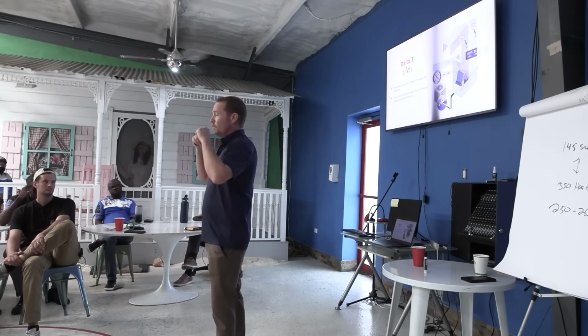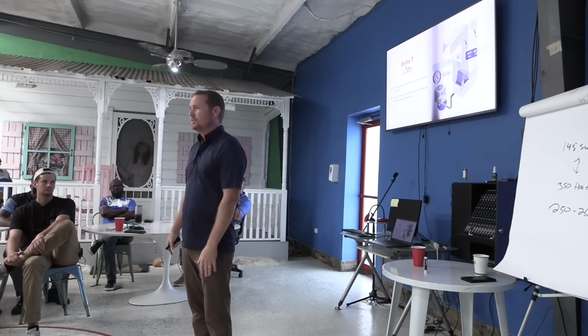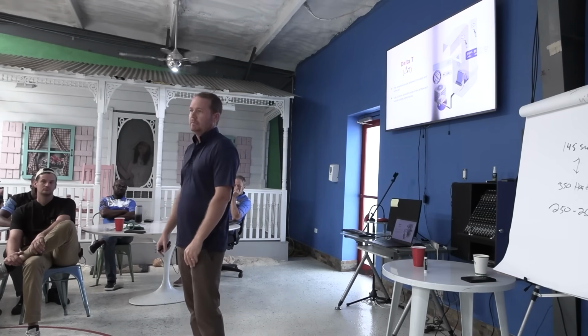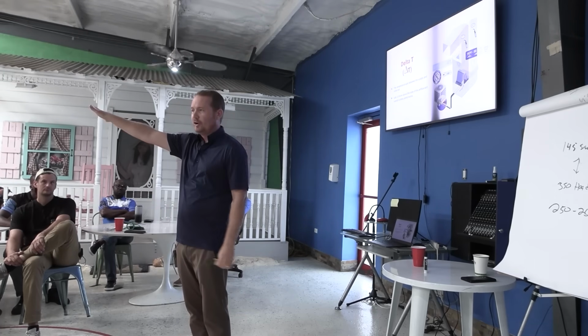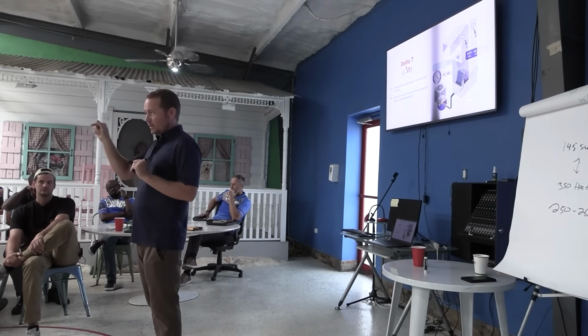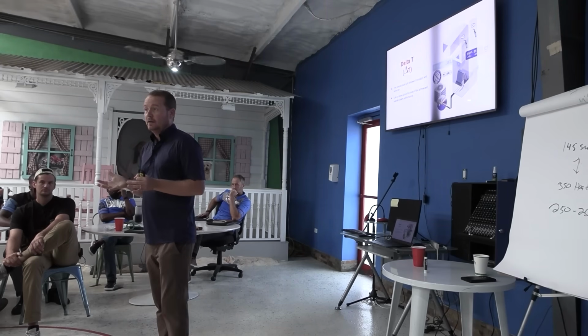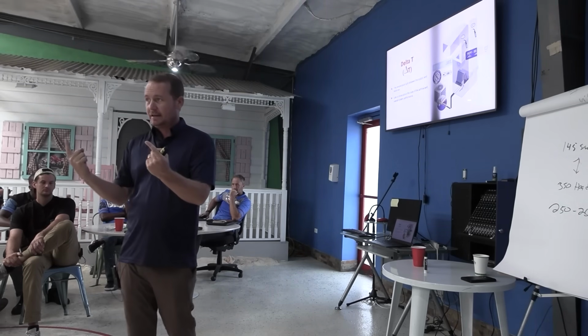And so for most of the country, people will say, yeah, 20, 22 degree delta T, that's about right. Most people say that. Forget those people, they don't know what we're dealing with. When we're measuring delta T, we're doing it for a different reason. Yes, it tells us a little about airflow, but it also tells us, hey, what's going on here, my delta T is low, everything looks like it's working right, moisture, this coil's dealing with a lot of moisture. And that's where using your senses as a diagnostician is huge.